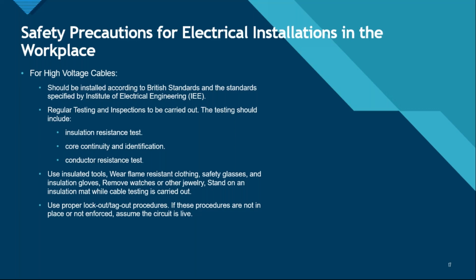Use insulated tools, wear flame resistant clothing, safety glasses, and insulation gloves. Always have your PPE in case there is an accident happening. Accidents can happen anytime, anywhere, so it's always better to have your PPE. Remove watches or other jewelry, and stand on an insulation mat while cable testing is being carried out. Use proper lockout tagout procedures. If these procedures are not in place or not enforced, assume the circuit is live.